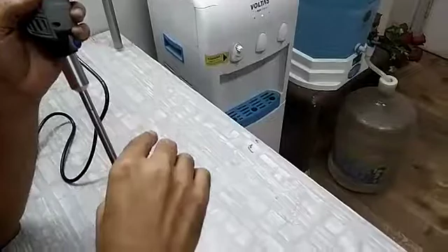So this is a very simple machine. Still, I hope this demo will help. And one or two more important points: once you run the sample, you should clean this probe. In the evening, the ideal thing is to take the rotor and stator out and clean and wipe them properly. If you are running many samples, in between the runs you can clean it so that there is no cross contamination. Run it in household bleach at a dilution of 1:10 in between. That will clean the probe for the next run.